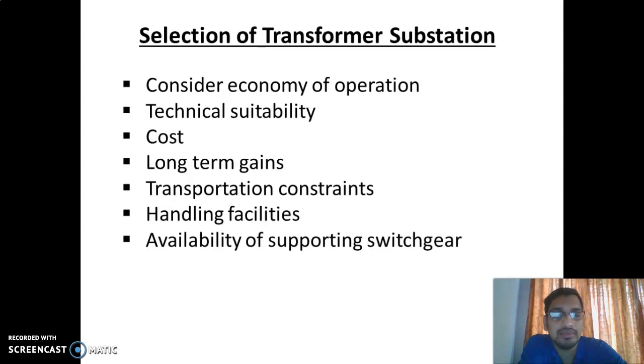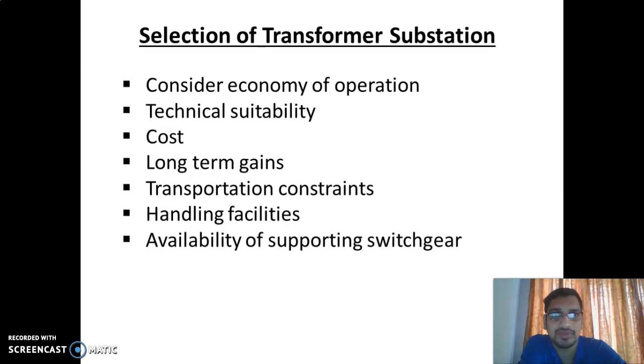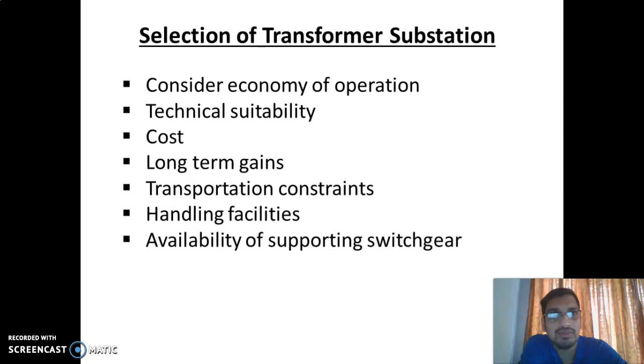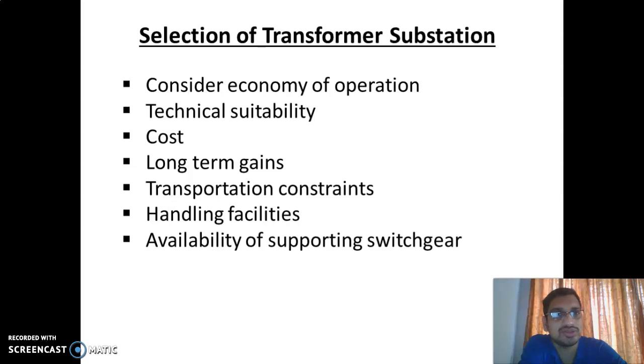In medium type industries, they get only the HT connection — 11 kV three-phase supply — so they should erect a separate transformer or substation in their premises. The connected load or maximum demand is above 50 kVA, then such kind of industry is known as medium type of industry, and they should install a separate substation or transformer.